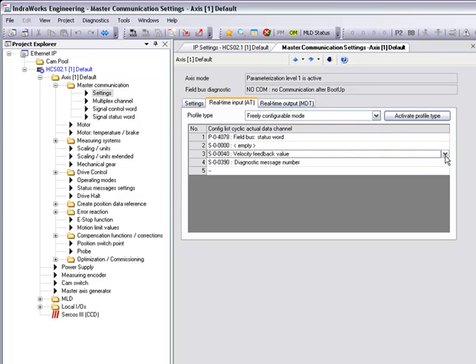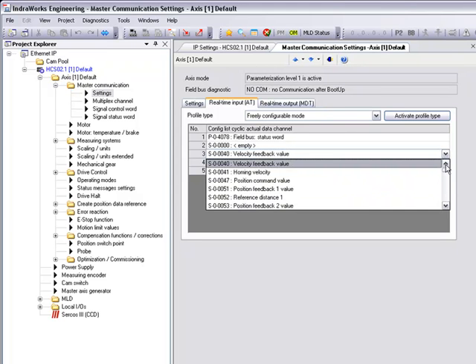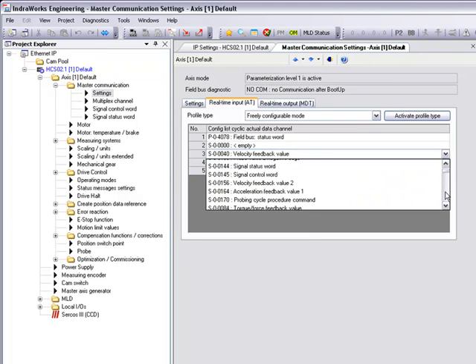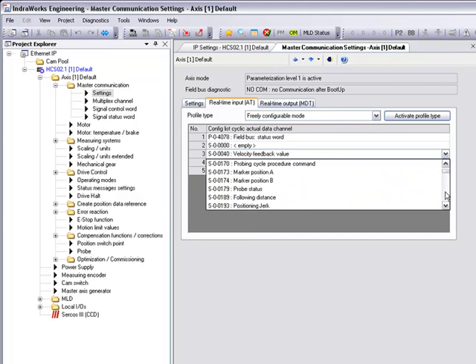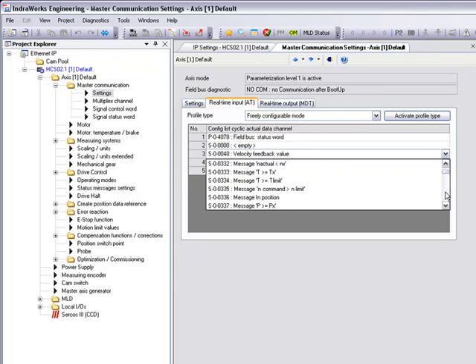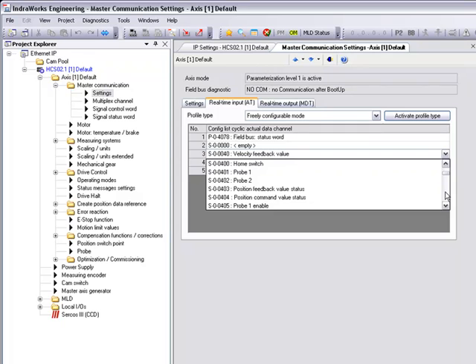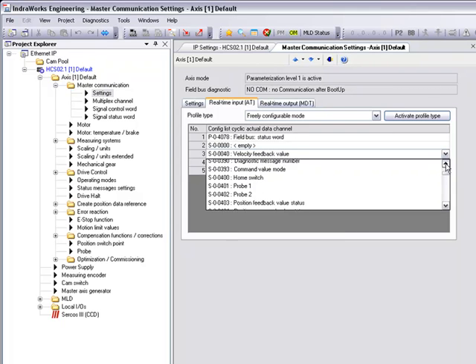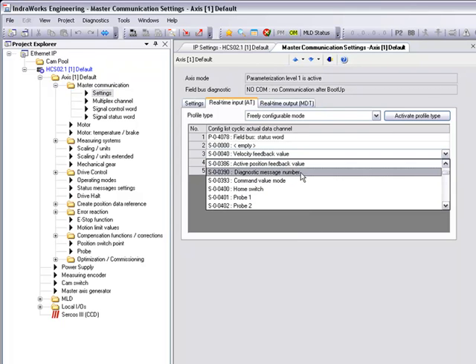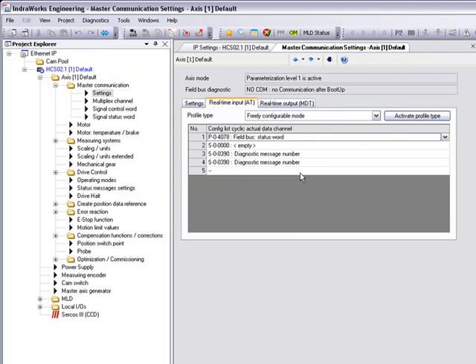Our real-time input configuration is what is sent back to our PLC as diagnostic and status information from the drive. Here we'll configure our velocity feedback value and also a position feedback value so our PLC knows the velocity and the position of our drive.